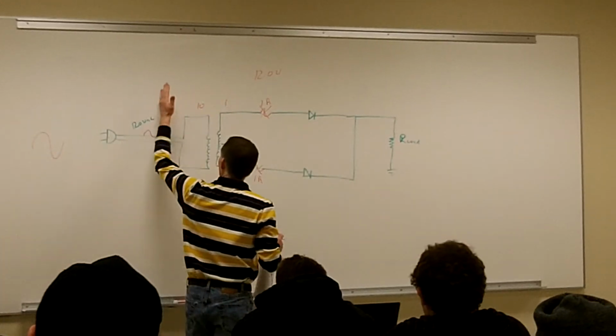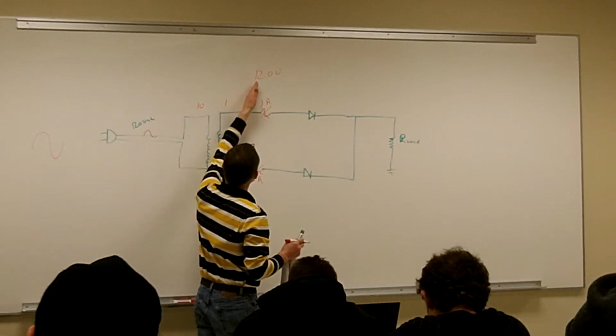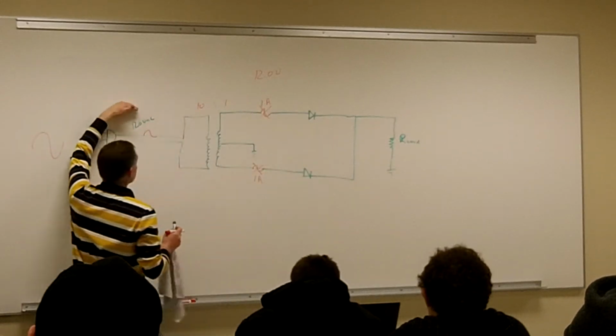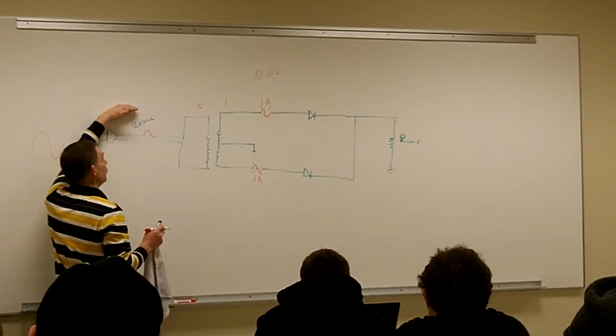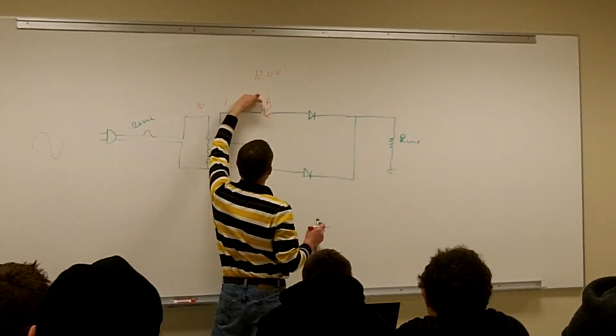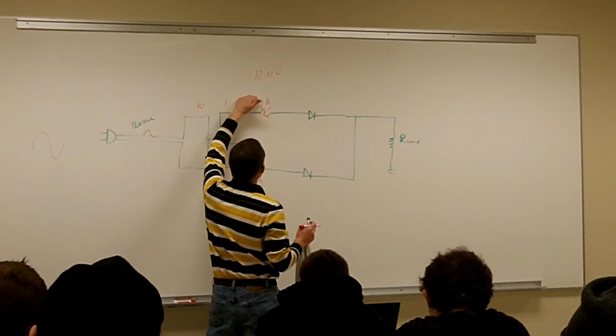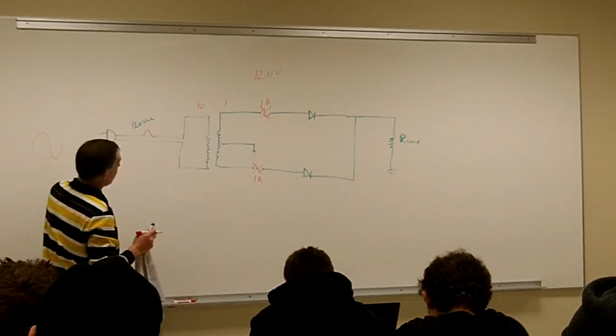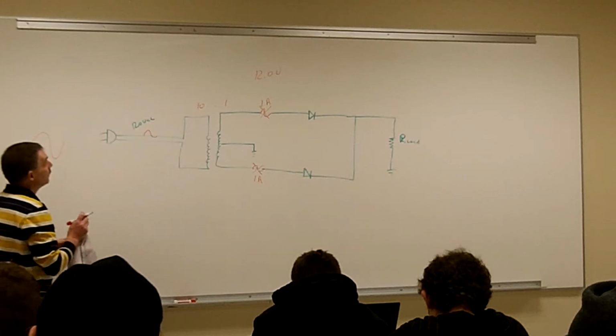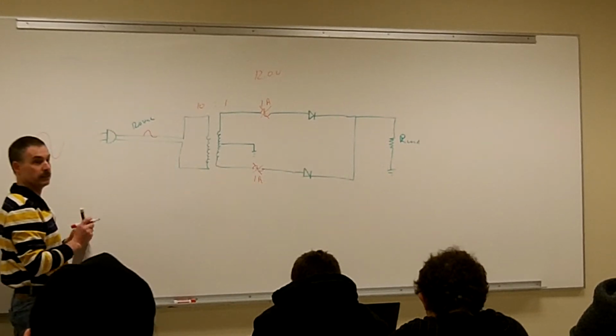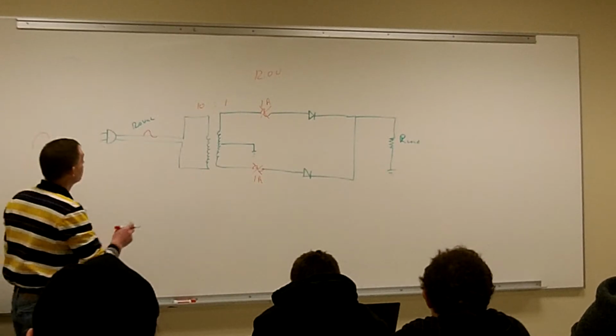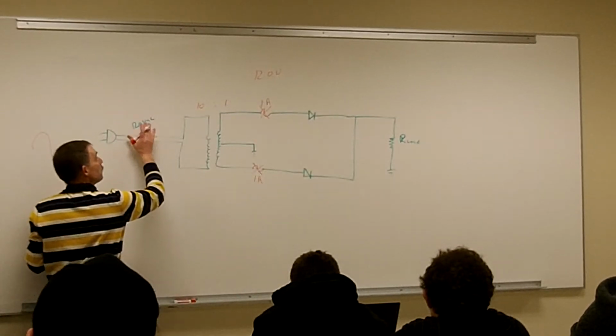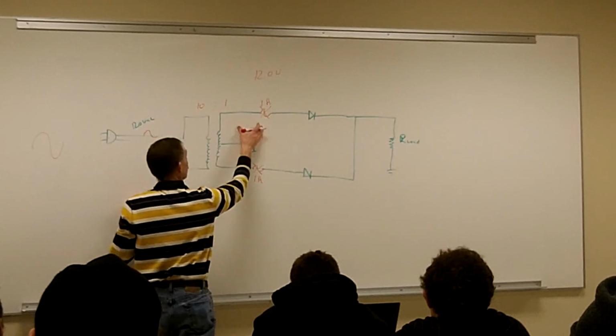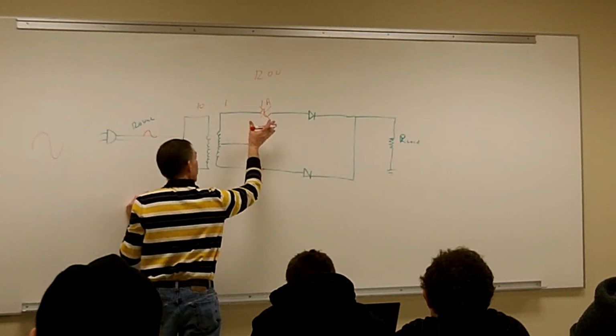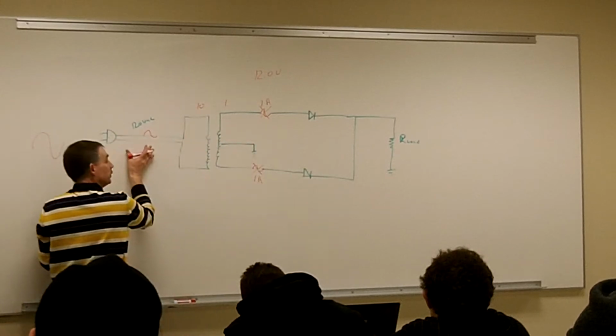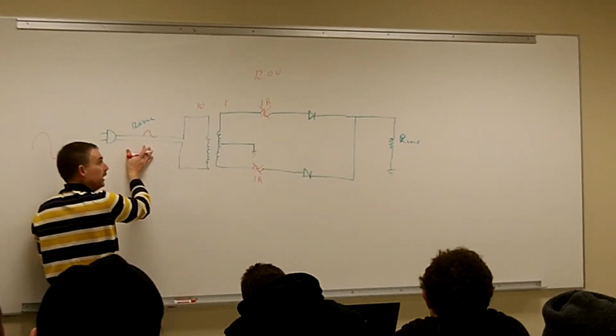So if we drop from 120 volts to 12 volts, what's my current going to be on this side? This is 12 volts with a maximum capability of 1 amp — what would be my maximum current on the primary side? 100 milliamps. Yep, because whatever we lose in voltage going to the secondary, we gain in current, and whatever we gain in current there, we lose on this side. The power always has to balance.